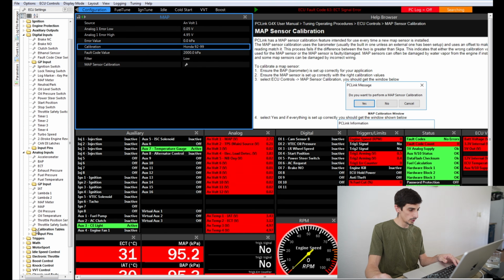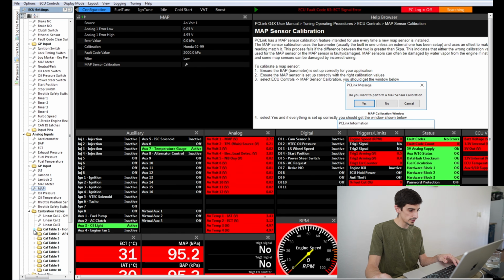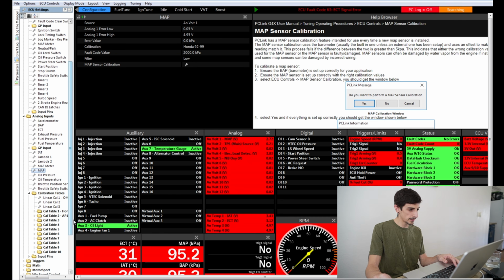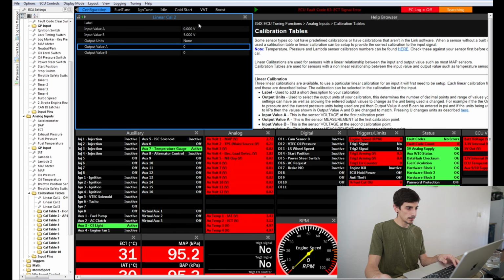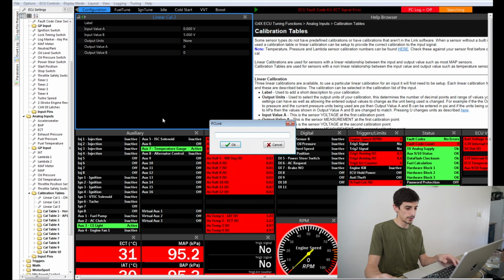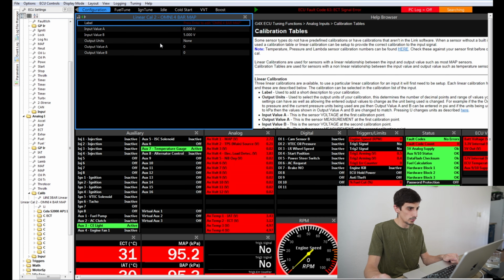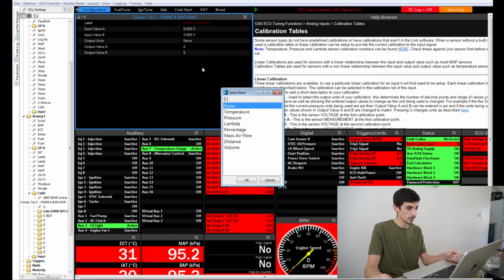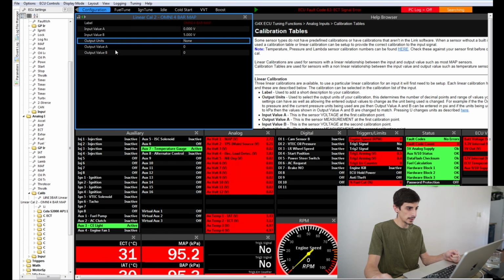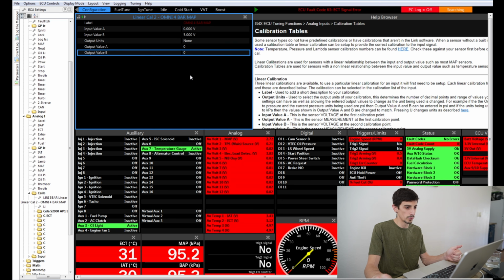We're going to go down into calibration tables and pick an empty slot, let's say calibration 2, and give it a name, like Omni 4-bar map. Essentially you would input the values from the manufacturer. Usually they'll supply the high and low values, what units they measure in, and what the reading is at 0 volts and at 5 volts.